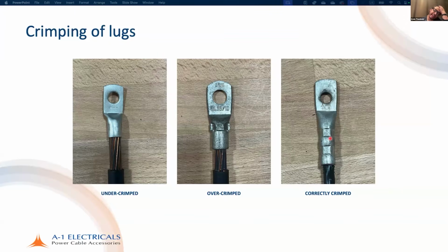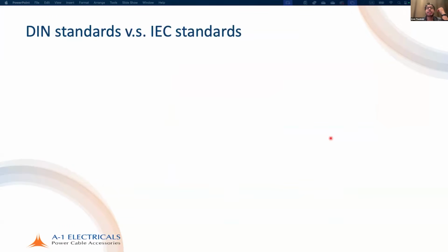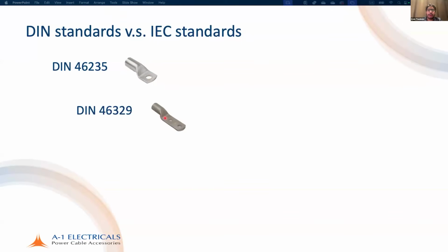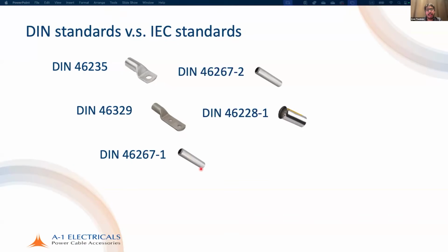Now, when it comes to crimping correctly, it's important to understand something beyond the IEC standards a little bit. There are these DIN standards, which provide dimensions as well. DIN 46235 provides a specification for cable lugs, compression type with a cover plate, ring type for copper conductors. DIN 46329 is cable lugs for compression connections, ring type for aluminum conductors. DIN 46267 Part 1 is a non-tension proof compression joint for copper conductors. DIN 46267 Part 2 is a non-tension proof compression joint for aluminum conductors. And DIN 46228 Part 1 is for bootlace ferrules without insulation. DIN 46228 Part 4 is with the insulation.